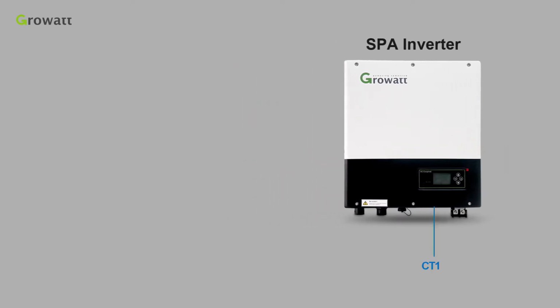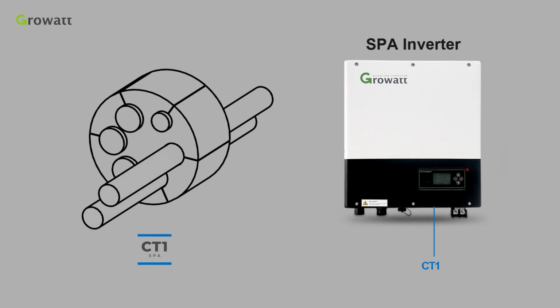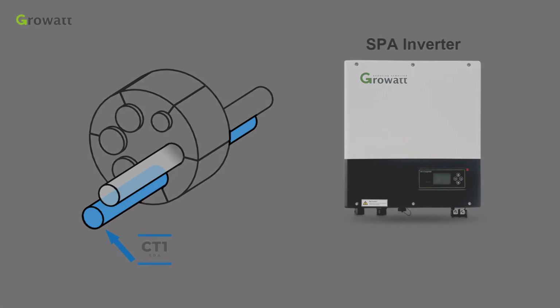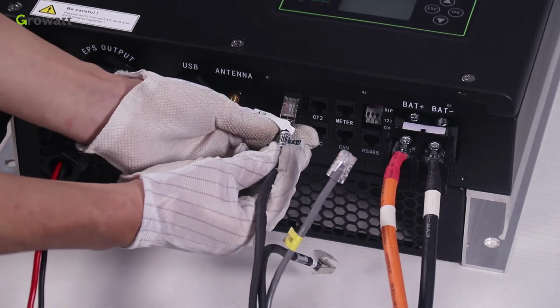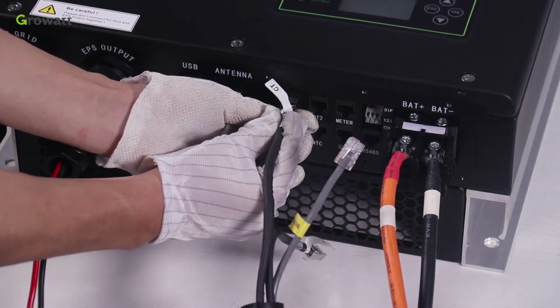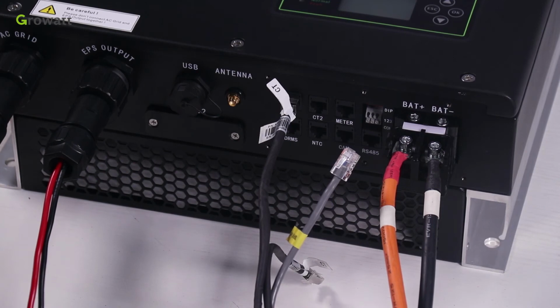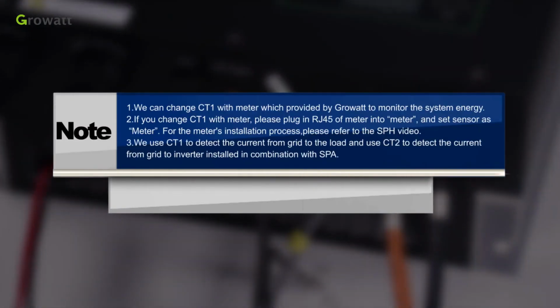Take CT1 for example. We need to route the CT1 cable through an opening in the cable support sleeve. Thread the CT1 cable through the cable gland. Insert the RJ45 plug of the network cable into the CT1 pin connector on the inverter until it snaps into place. Note 1. We can change CT1 with a meter, which is provided by Growatt to monitor the system energy.